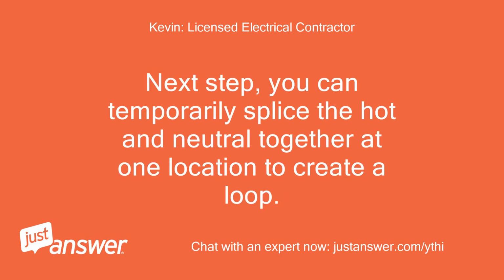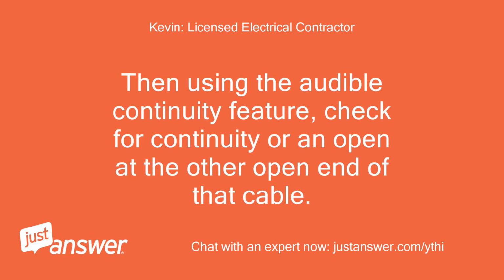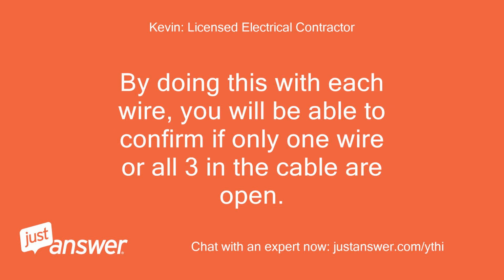Next step, you can temporarily splice the hot and neutral together at one location to create a loop. Then, using the audible continuity feature, check for continuity or an open at the other open end of that cable. By doing this with each wire, you will be able to confirm if only one wire or all three in the cable are open.